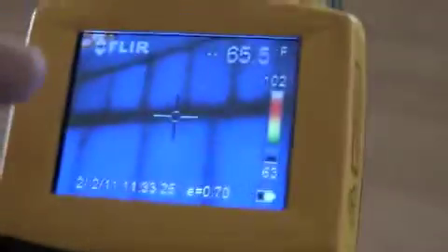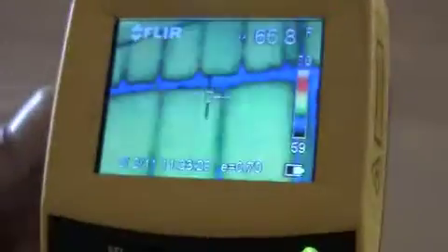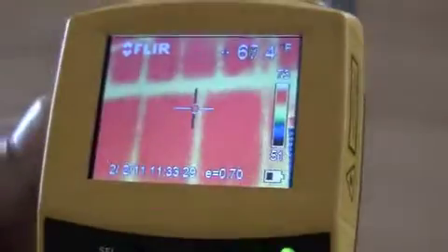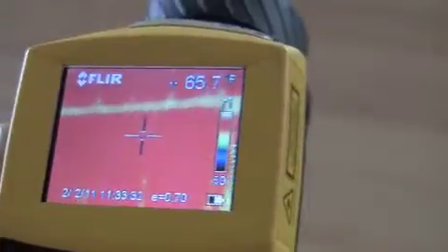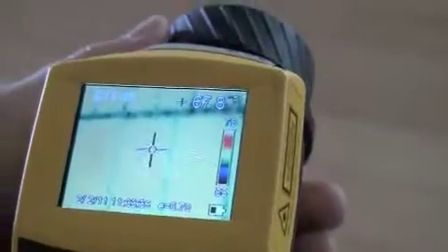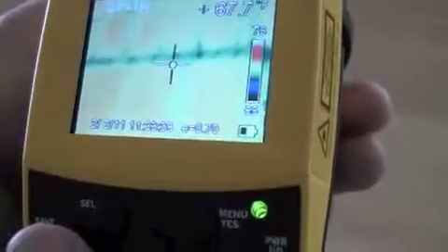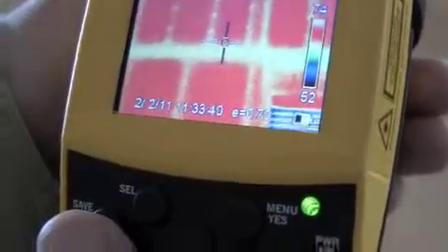And then why do other parts of the wall look better? Well, they're not necessarily looking any better. What you can see is the thermal bridging with the studs and the insulation being in the center. So the center wall actually performs a lot better than where the thermal bridging of the studs is, and that's typical of most homes.